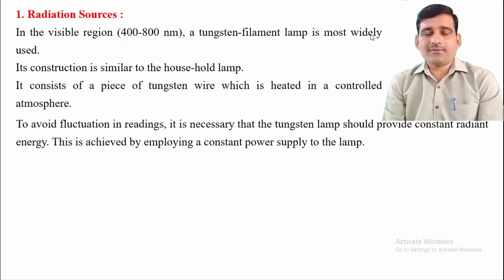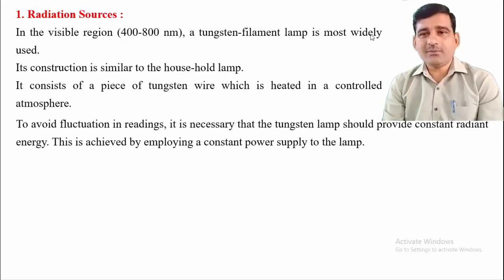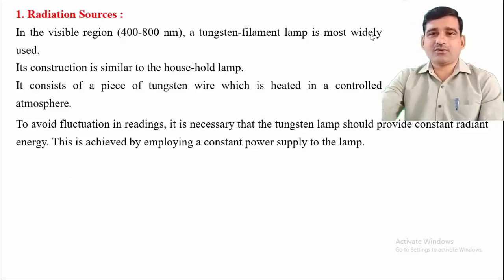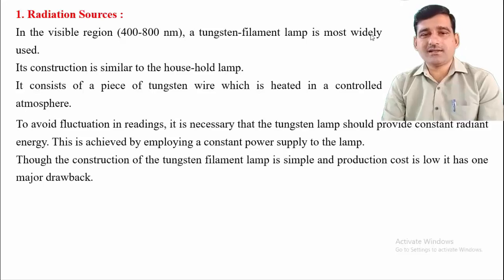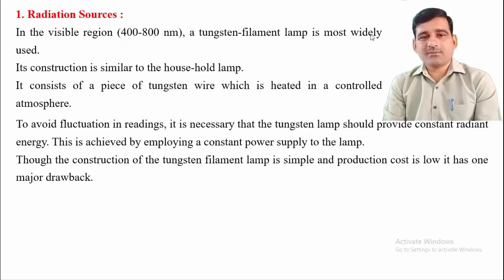To avoid fluctuations in readings, the tungsten lamp must be provided a constant power supply so that it delivers continuous radiation. Although the construction is simple and the production cost is low, this lamp has one major drawback.